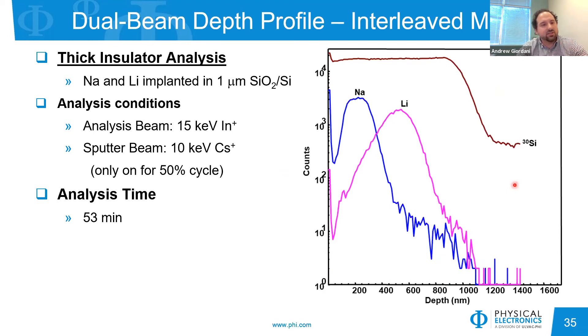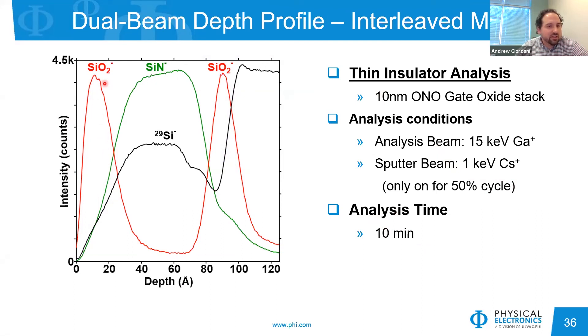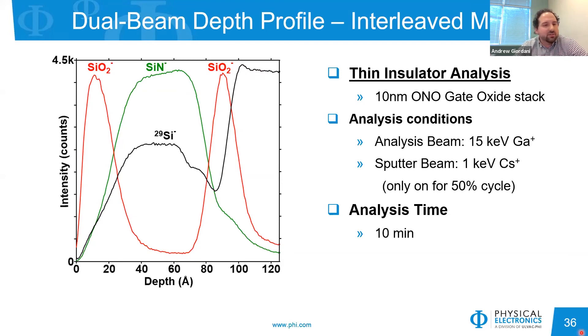Interleave mode also works well for thin insulating samples with very high data point density. A 10 nanometer oxide-nitride-oxide gate oxide stack is profiled using 15 kV gallium for the analysis beam and 1 kV for the sputter beam, providing much higher depth resolution. The analysis took only 10 minutes. Sputtering down through the sample reveals the surface oxide at roughly 2 nanometers, the silicon nitride signal increasing then decreasing, and finally the last oxide before the substrate. Operating at low impact energy gives high depth resolution and ensures no interfaces are missed due to the high data point density.